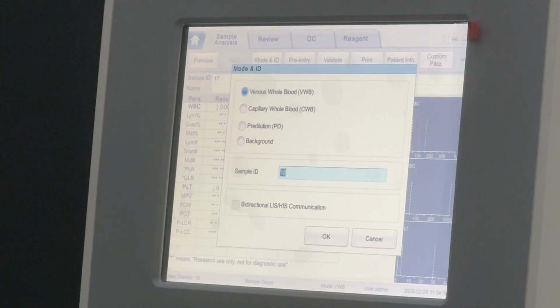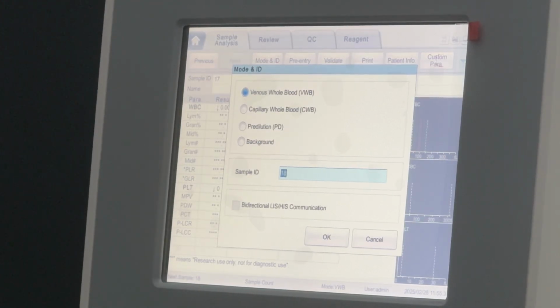The next thing I'm going to tell you is that we have 2 modes, which are very important. Venous whole blood, which, as you doctors know, the GP takes from the syringe, and the blood goes into a K2 EDTA bottle. Or we have a pre-diluted mode. Pre-diluted mode is for samples like baby samples or old people, where there is very little sample. For that reason, we need to use the pre-diluted mode. With the minimum sample, the machine can analyze and generate the result with a minimum of 9 microliters of blood.